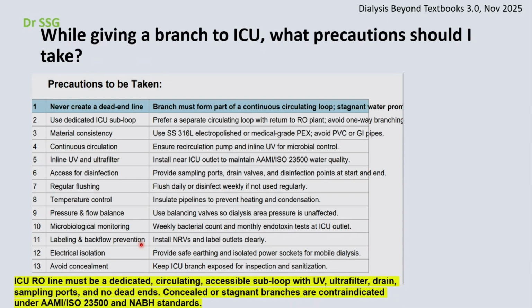While giving a branch to the ICU, it should be a part of the continuous loop. We usually use a branch with a loop incorporated, so that it is separately returned to the main RO tank. And it should be of the same material as your entire system, because people tend to take shortcuts.